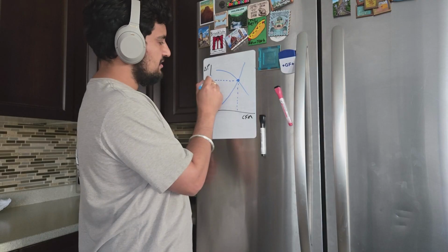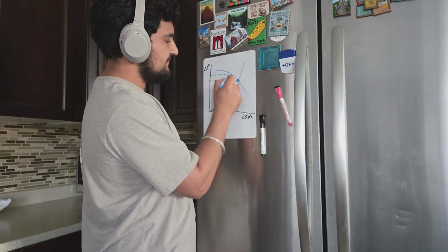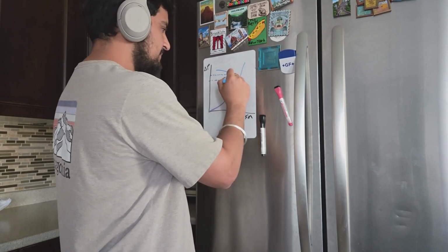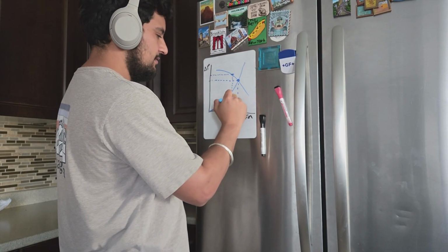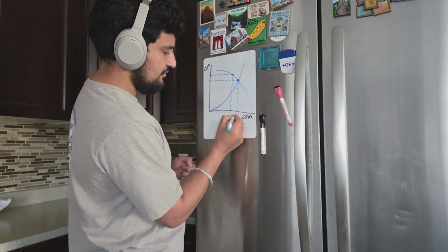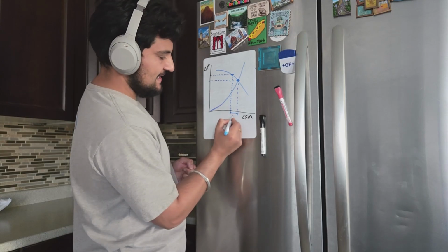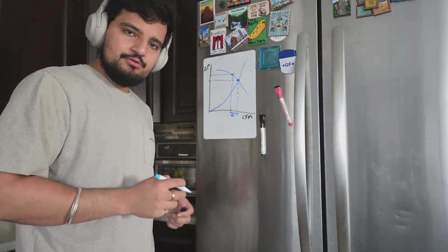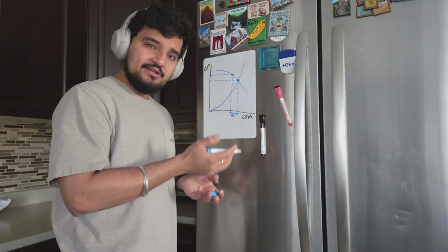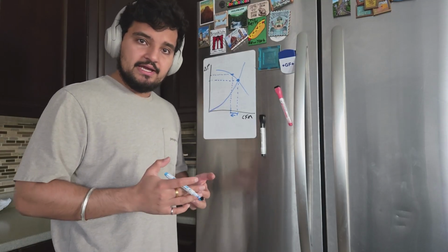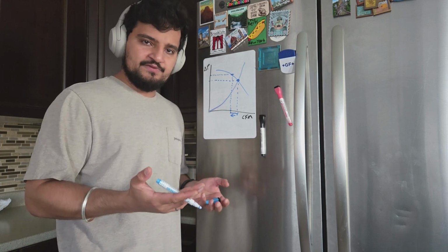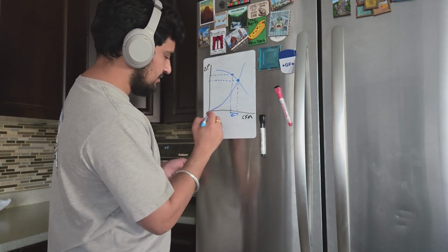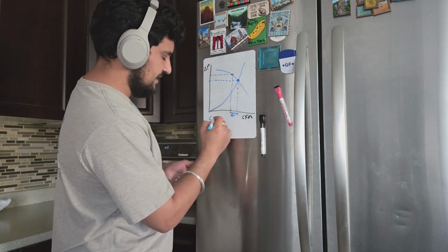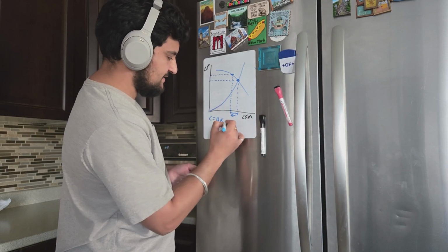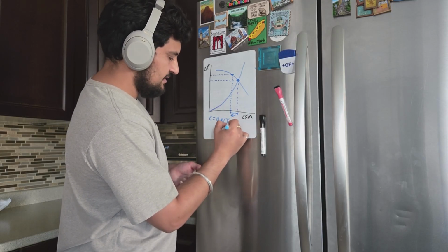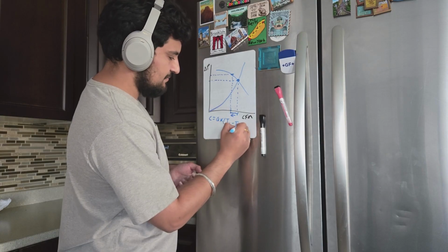Now this new pressure, if you draw a straight line from it, it intersects the fan curve somewhere here, which means if you draw a vertical line down, that's your new flow rate. So your flow rate has decreased by this amount. So now you're actually delivering less air through your ductwork and consequently less air through each of the rooms in your house. And as we talked about before, your cooling capacity is related to the flow rate times some constant K times the room temperature minus the supply temperature.